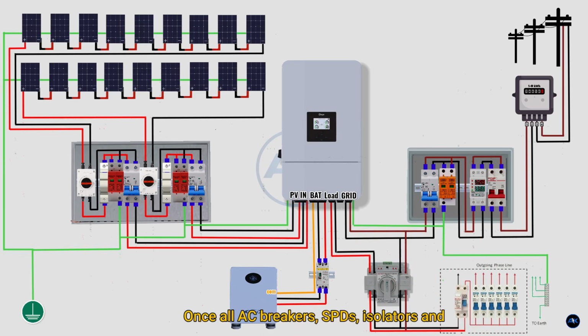Once all AC breakers, SPDs, isolators, and relays are installed and tightened, double-check every termination. Verify that line, neutral, and ground are correctly positioned and that the wiring routes are clean, organized, and free from sharp bends. With the AC side connected, the hybrid inverter is now fully integrated into the home's electrical system.